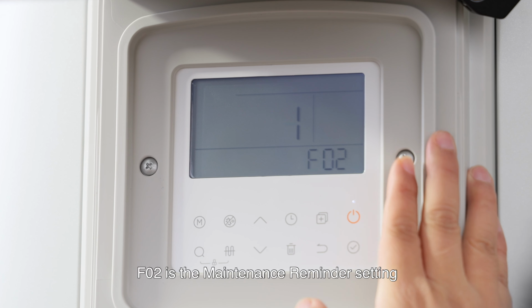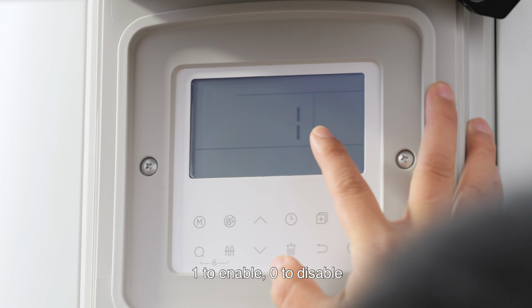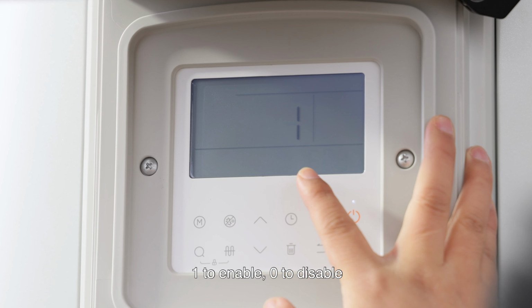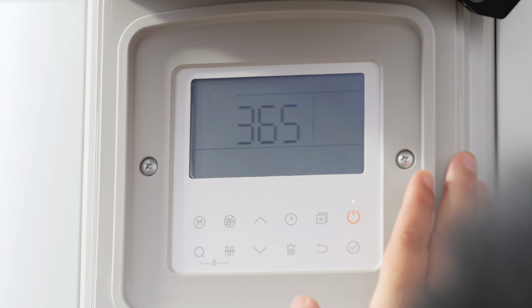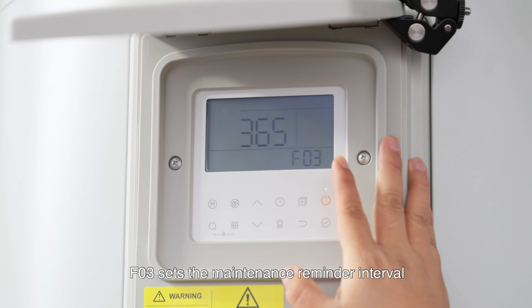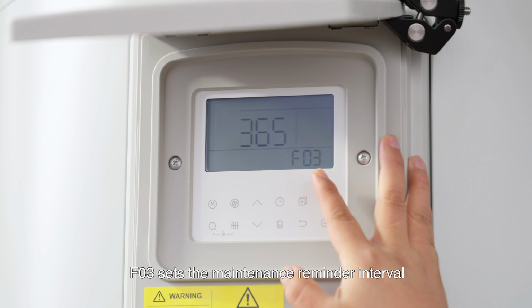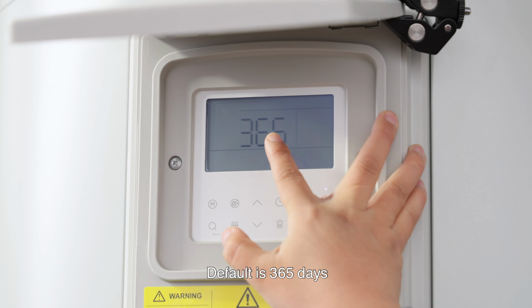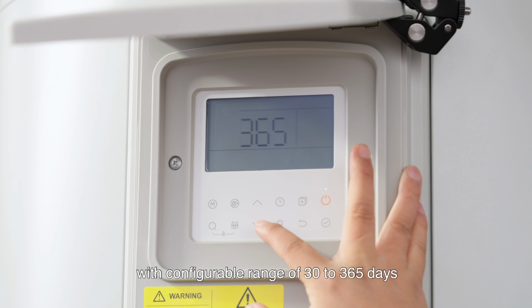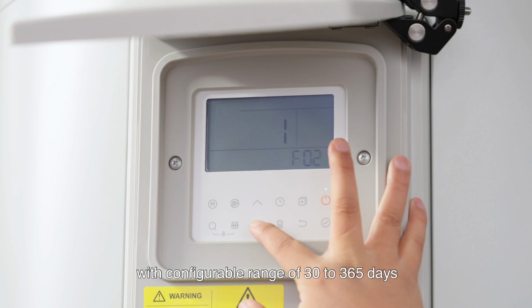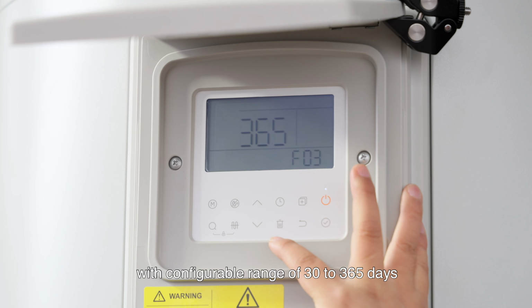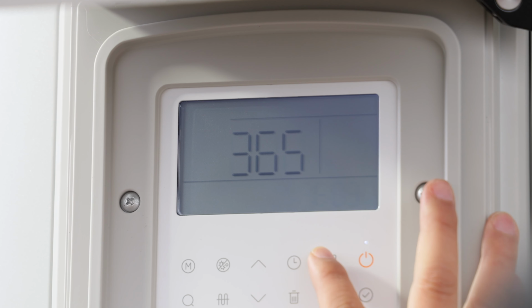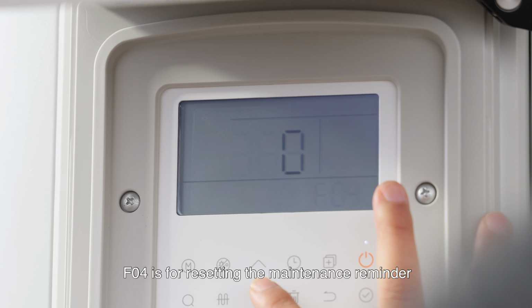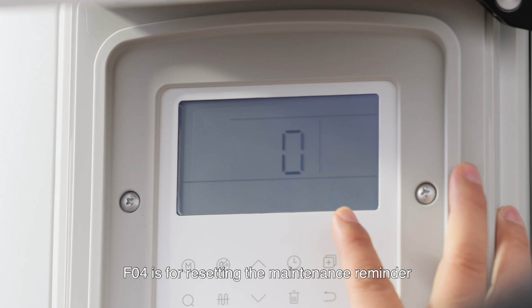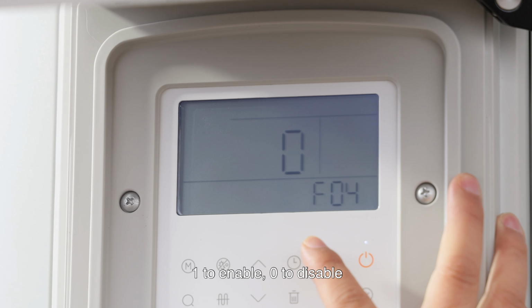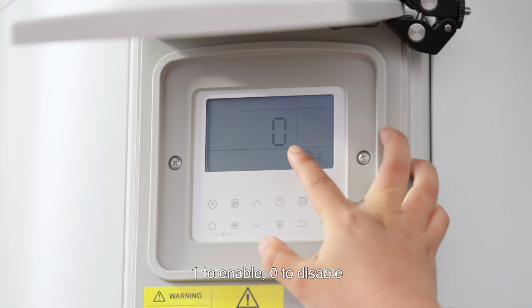F02 is the maintenance reminder setting, 1 to enable, 0 to disable. F03 sets the maintenance reminder interval. The default is 365 days, with a configurable range of 30 to 365 days. F04 is for resetting the maintenance reminder, 1 to enable, 0 to disable.